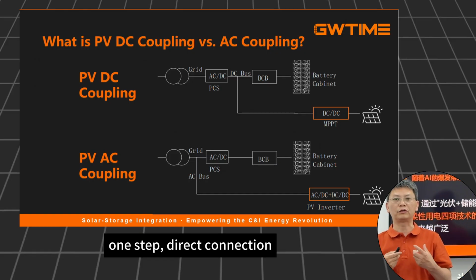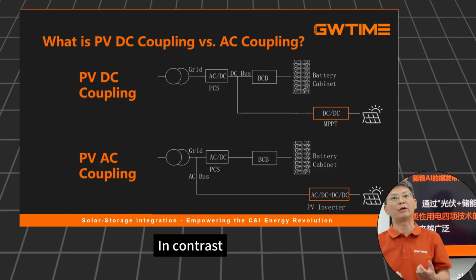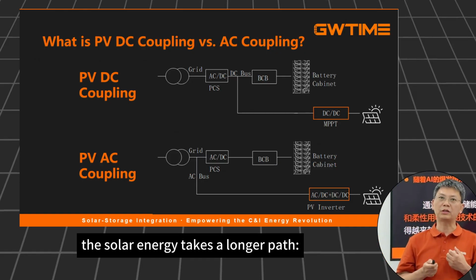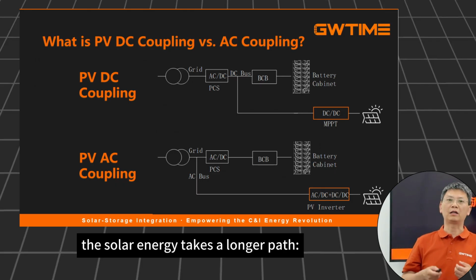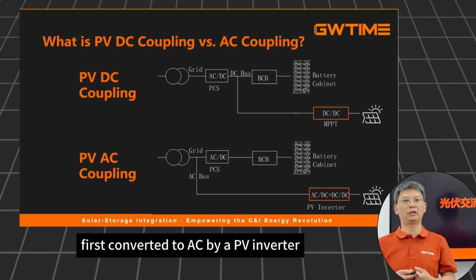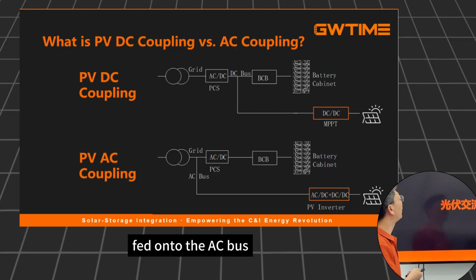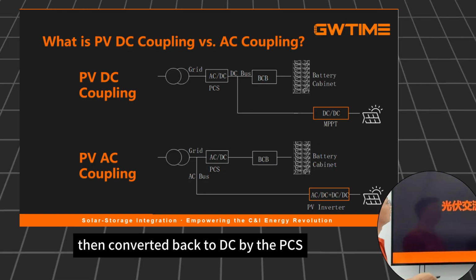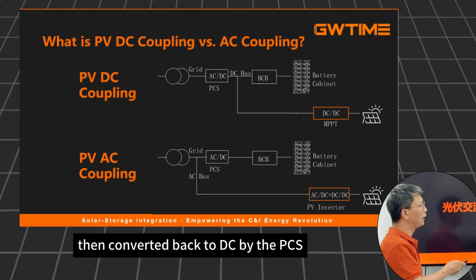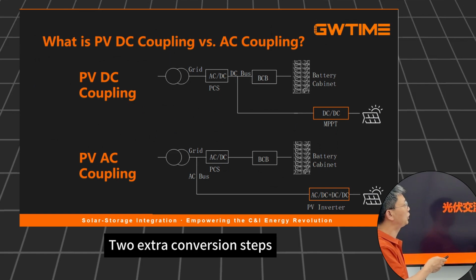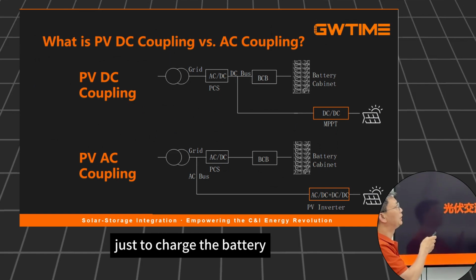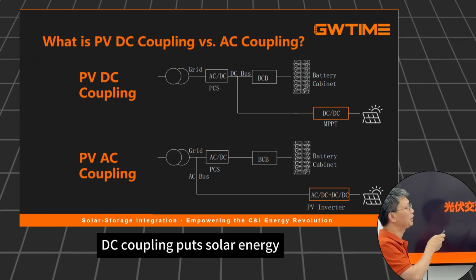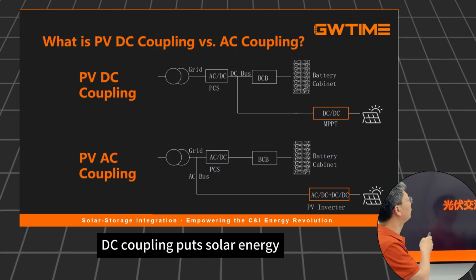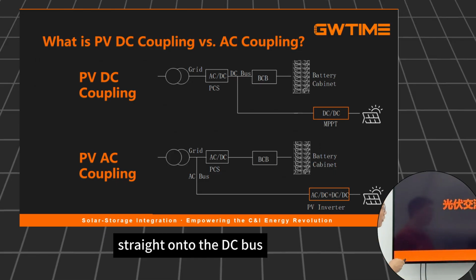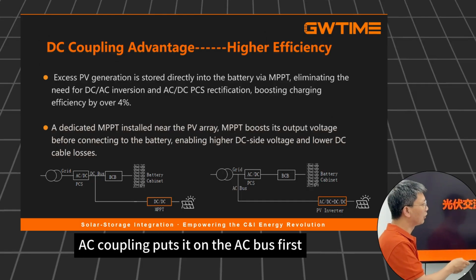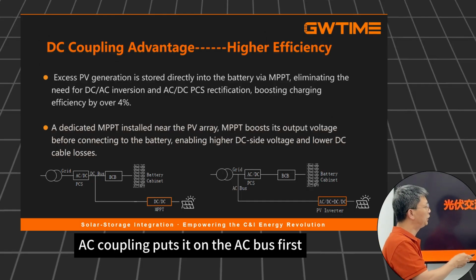One step, direct connection. In contrast, in an AC-coupled system, the solar energy takes a longer path. First converted to AC by a PV inverter, fed onto the AC bus, then converted back to DC by the PCS before reaching the battery. 2 extra conversion steps just to charge the battery. The key difference: DC coupling puts solar energy straight onto the DC bus. AC coupling puts it on the AC bus first.